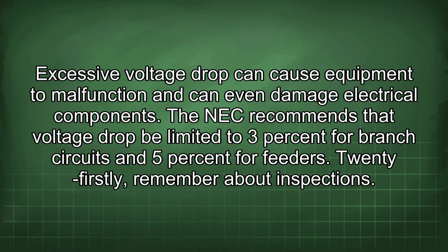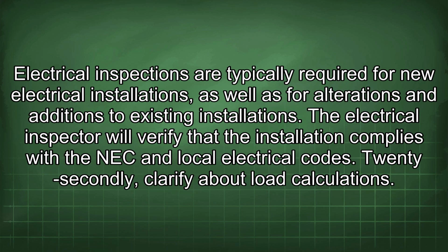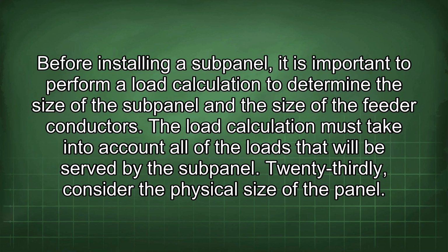21stly, remember about inspections. Electrical inspections are typically required for new electrical installations, as well as for alterations and additions to existing installations. The electrical inspector will verify that the installation complies with the NEC and local electrical codes. 22ndly, clarify about load calculations. Before installing a subpanel, it is important to perform a load calculation to determine the size of the subpanel and the size of the feeder conductors. The load calculation must take into account all of the loads that will be served by the subpanel.